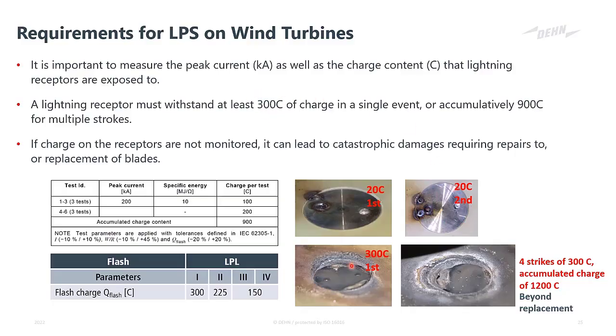When we go up to the limit of 300 coulombs, you can see that the damage is more around the outside of the receptor, and it starts damaging the blade, but this can still be repaired by only replacing a receptor. If we don't do this, and we don't monitor the amounts of lightning strikes and the amounts of charge onto those receptors, you can see on the right, this is an example of 4 300 coulomb strikes, which is an accumulated charge of 1,200 coulombs on a single receptor. And they are only able to withstand 900 coulombs cumulatively if they're manufactured according to standard. And you can see that the replacement becomes much more difficult. So this receptor is beyond replacement, and that means that you have to start cutting out portions of the blade and do repairs to the blade itself, and that creates longer downtimes and bigger unplanned maintenance.